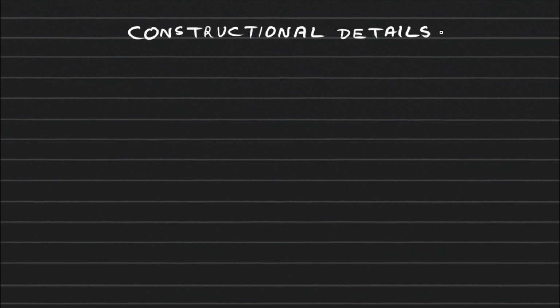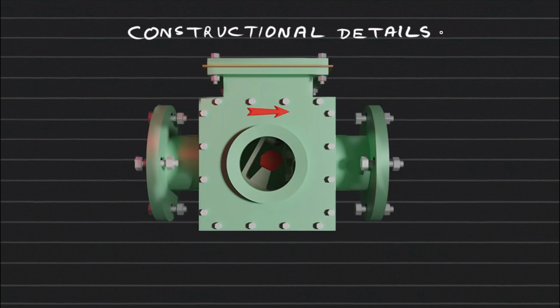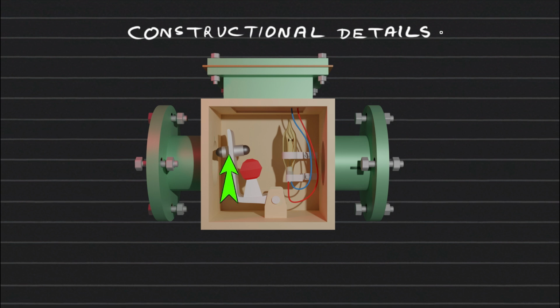Construction details. Now let's talk about the construction of the oil surge relay. The OSR consists of a metallic casing that acts as a small oil chamber. It has an inlet connection from the diverter tank and an outlet connection going towards the conservator. Inside the chamber, there is a flap or vane mechanism. A small permanent magnet is attached to this flap. Under normal breathing or slow oil movement, the velocity of oil flow is not enough to move the flap. So the relay remains in its normal position.